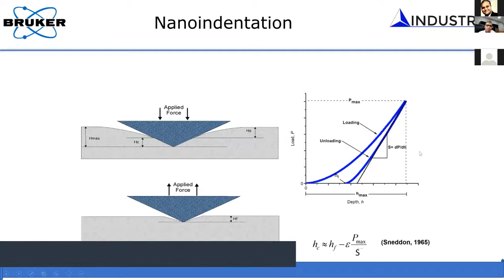And now I think I already covered that you can use this transducer to generate load displacement curves. And these load displacement curves are unique to the specimen material that we use. We call it a mechanical fingerprint. And from the unloading curve, you can measure the stiffness. And from knowing the stiffness and the area of the tip by the calibration process, you can calculate the reduced modulus and hardness of the material.